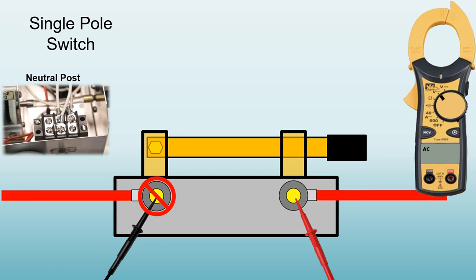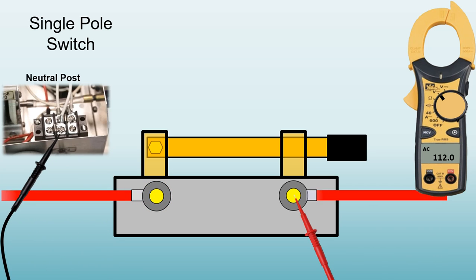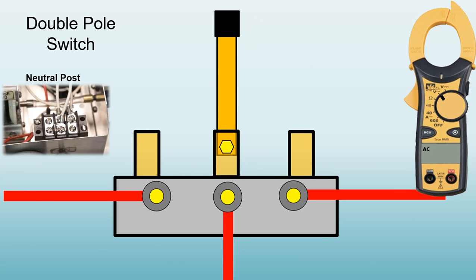We now put our meter leads on the switch. This is the wrong way to test a switch. When testing a switch for current running through it, we take one of our meter leads and put it back on a common or a neutral post, and one to the opposite side of the switch to see, do we have current flowing through the switch?